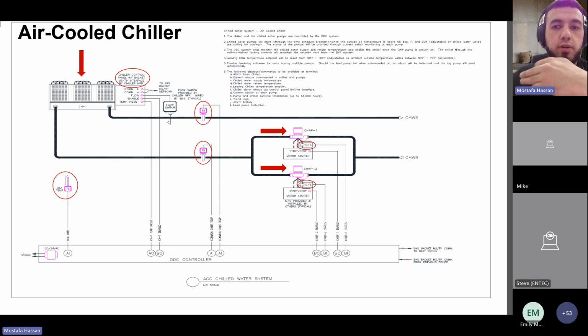You have your chilled water supply and return temperature sensors. Both of these will be monitored. And then you have a chiller alarm status. Again, that's the same alarm coming from the control panel of the chiller factory controls. And then pump and chiller runtime. You want to know how long each pump is running for, up to 64,000 hours. It's specified up to 64,000 hours and needs to be logged. And then you have some trend logs, alarm history, and lead pump indication. Which one is actually the lead pump in the system?